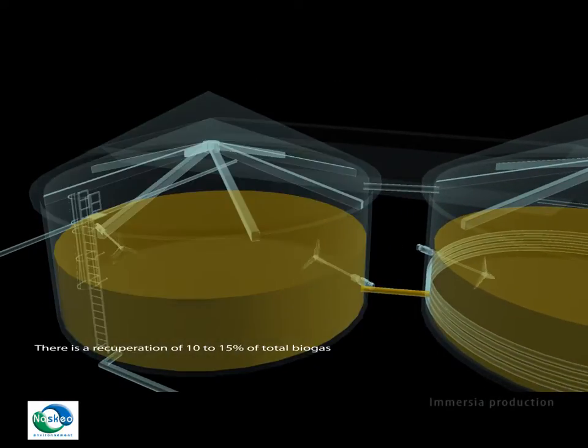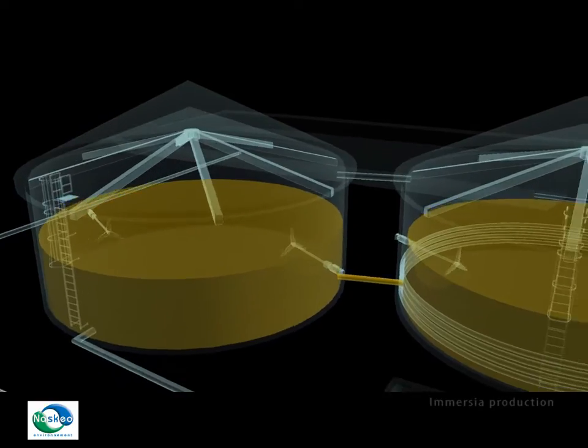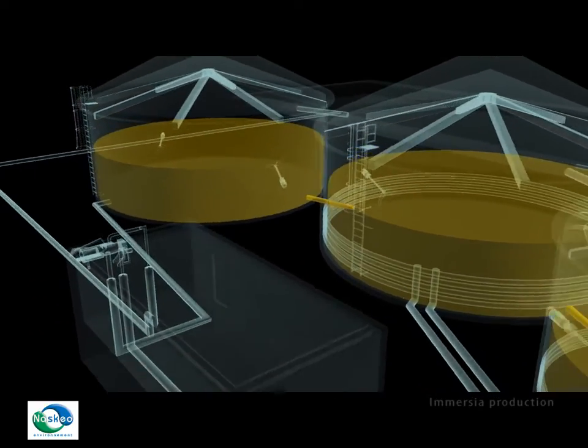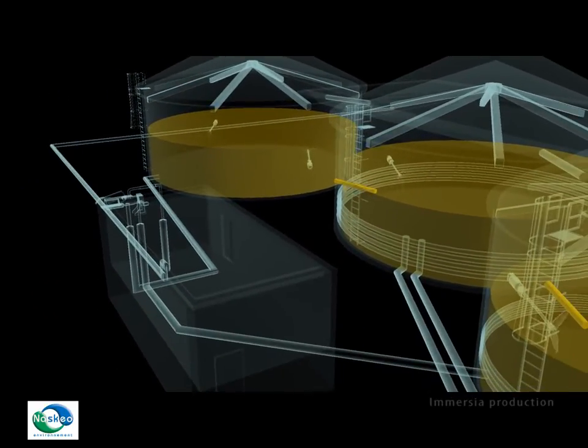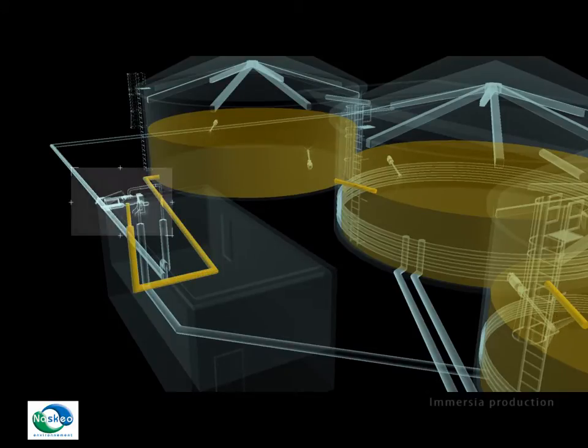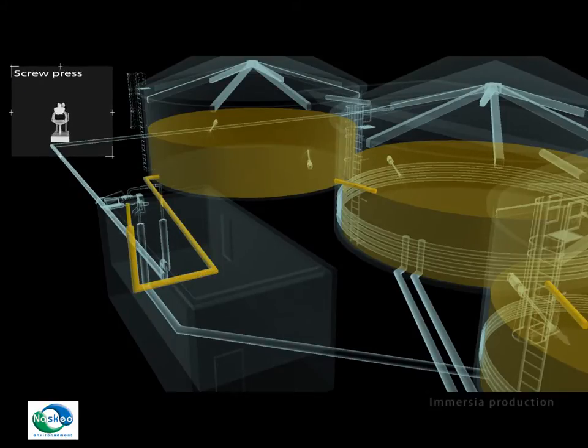The maturation stage allows a stabilization of the digested sludge for one month and anaerobic digestion stops here. After the maturation tank, digested sludge is separated through a screw press and stored. It is then used as fertilizer.